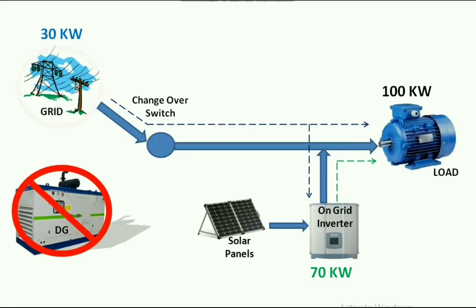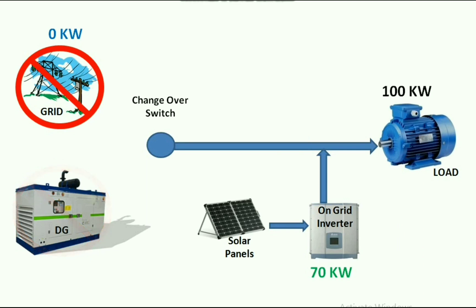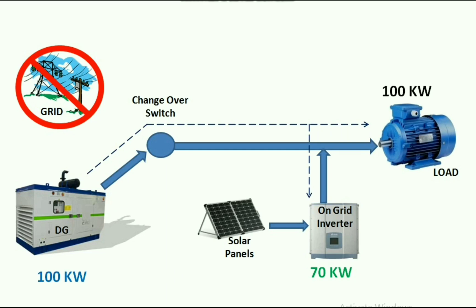So the load gets 70 kW from the solar inverter and 30 kW from the grid. When the grid cuts off, power from the grid stops flowing to the load and inverter, and becomes zero. As it is an on-grid inverter, it stops generating solar power. With no grid, the DG starts and supplies power to the load and inverter. Initially the full 100 kW load is supplied by the DG. After getting supply from the DG, the on-grid inverter starts generating solar power and shares the load — 70 kW by the solar inverter and 30 kW by DG.